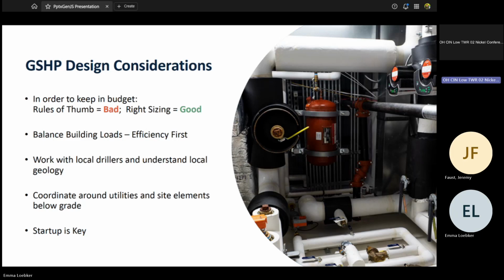The other big piece of geo-exchange systems is balancing loads. If you only need heating, over time you'll pull a lot of heat out of the ground, and especially in closed loop systems, that imbalance requires a larger well field. The same is true for cooling-only applications. The more balanced the heating and cooling demand, the smaller the heat exchanger or ground system you need. That's why district systems make sense, as Dave mentioned, since they achieve balanced loads across multiple building types. But even within your own building, designing and optimizing loads to reduce heating and cooling and balance them goes a long way toward reducing the upfront cost of your ground source heat exchanger.